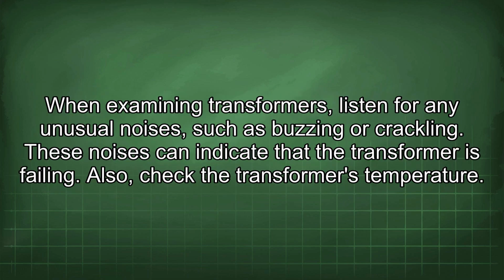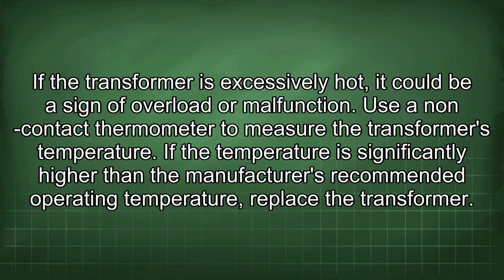When examining transformers, listen for any unusual noises, such as buzzing or crackling. These noises can indicate that the transformer is failing. Also, check the transformer's temperature. If the transformer is excessively hot, it could be a sign of overload or malfunction. Use a non-contact thermometer to measure the transformer's temperature. If the temperature is significantly higher than the manufacturer's recommended operating temperature, replace the transformer.